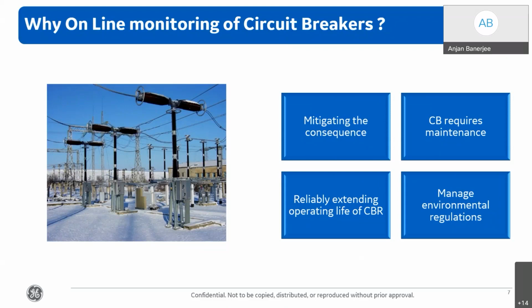The result would be initiation of the busbar protection scheme and unintentional tripping of the bus. So proper care of the circuit breaker is required to mitigate this severe consequence by implementing an online monitoring solution of the circuit breaker, which would help us in condition-based monitoring.